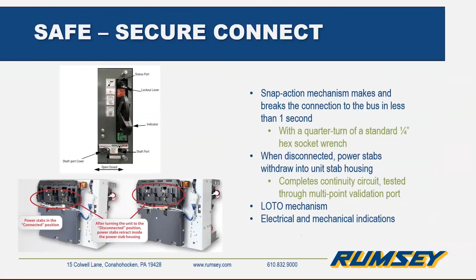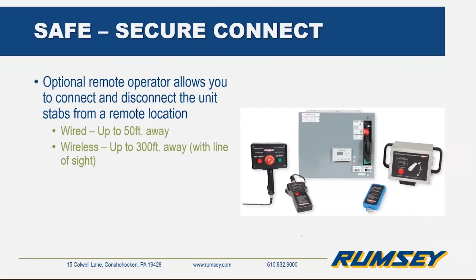You can even take SecureConnect a step further, literally, by adding remote operator. And what this is, it provides a wired or wireless connection to the unit, and it allows you to disconnect the unit from power while staying away from the MCC. So it's the same SecureConnect feature. You're just putting, I think it's the device in this picture here, the device all the way on the right, on the unit door, and then you have your controller, whether it's wired or wireless, and it makes that disconnect function while you're standing away from the MCC. And again, it's just an optional safety feature, and it's designed to reduce exposure to electrical hazards.